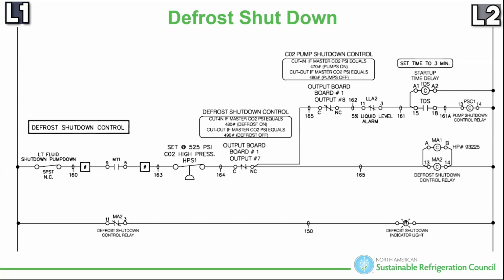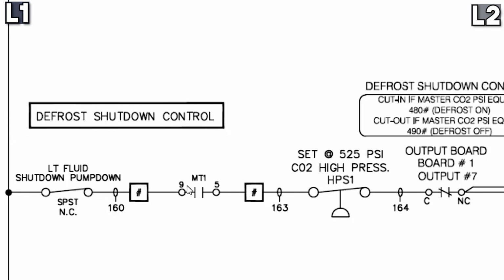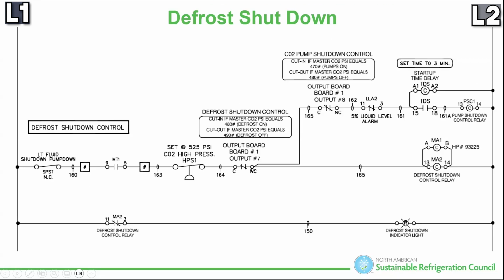I put my red lead there. I got 208. Good. If I got 208, which way do I go? Well, I don't go that way, because that means that's closed. My pressure's not high, and this output board is closed, because otherwise I would not have voltage. So since I have voltage, I'm headed this way. If I wouldn't have voltage, I'd go back this way, probably to this pin here.